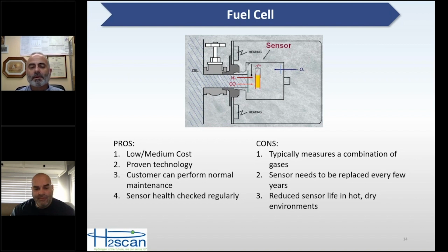The other thing to keep in mind is when you make the fuel cell, there's 2 pieces of metal with an electrolytic gel in between. So the yellow stuff is an electrolytic gel. The reason that the fuel cells eventually fail is that that gel dries out over time and loses its properties from when it was a nice fresh sensor. And so if you're in a hot, dry environment, the electrolytic gel will dry out faster, and you will get reduced life of the sensors. And to the contrary, if you're in a very moist environment, your sensors, I think, would tend to last longer. Okay.